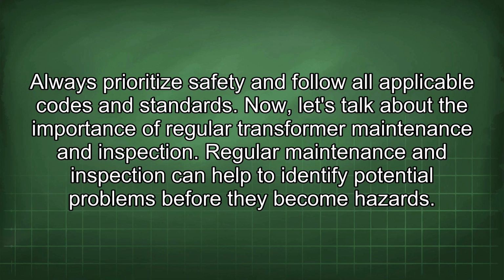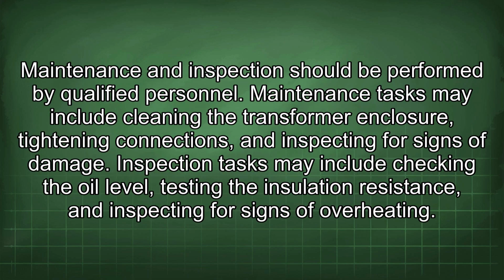Now, let's talk about the importance of regular transformer maintenance and inspection. Regular maintenance and inspection can help to identify potential problems before they become hazards. Maintenance and inspection should be performed by qualified personnel. Maintenance tasks may include cleaning the transformer enclosure, tightening connections, and inspecting for signs of damage. Inspection tasks may include checking the oil level, testing the insulation resistance, and inspecting for signs of overheating.